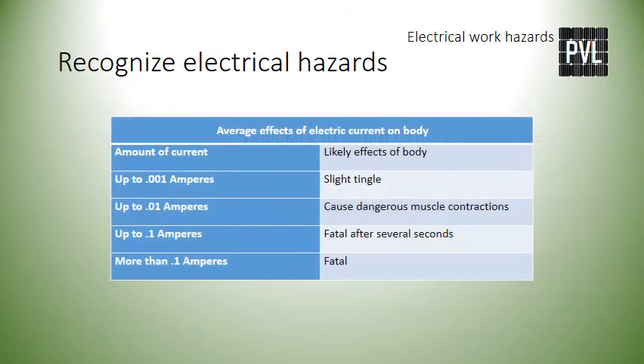On the screen now, you can see the average effects of electric current on the body. On the left column we see the amount of current; on the right column we see the likely effects. Up to 0.001 amperes you can feel a slight tingle. Up to 0.01 amperes could cause dangerous muscle contractions. Up to 0.1 amperes could be fatal after several seconds. And more than 0.1 amperes is usually fatal.